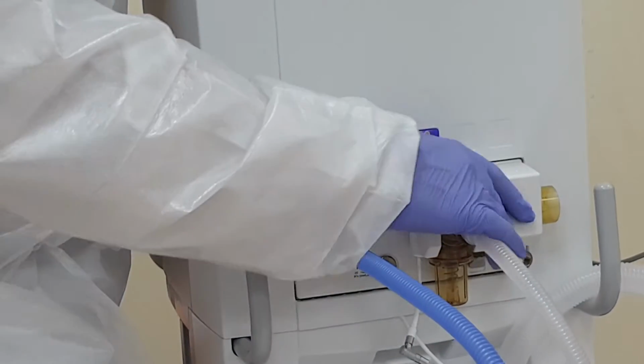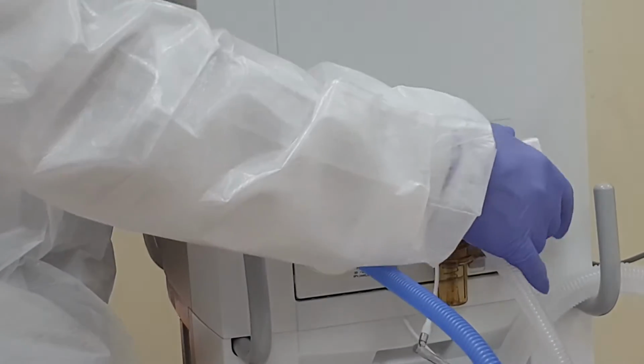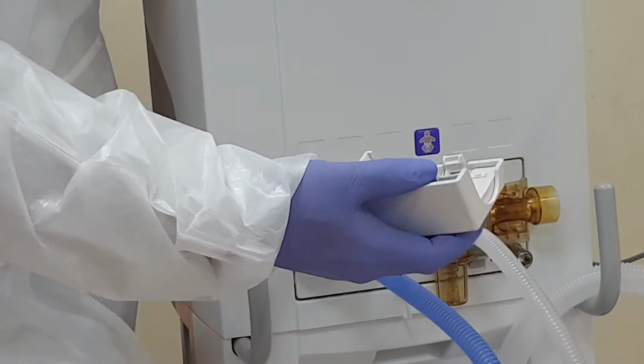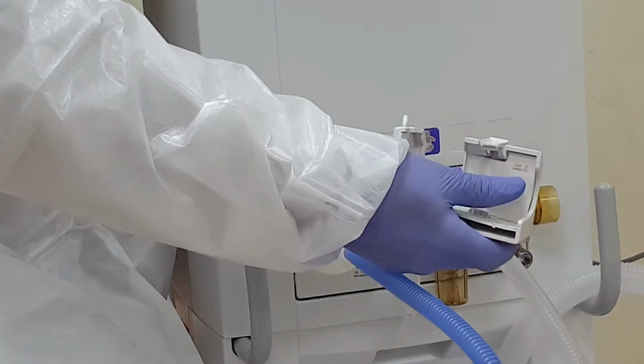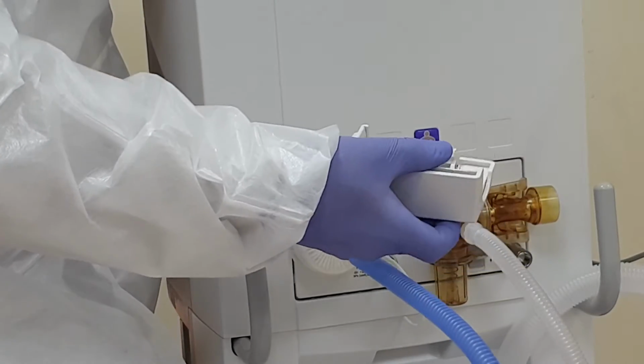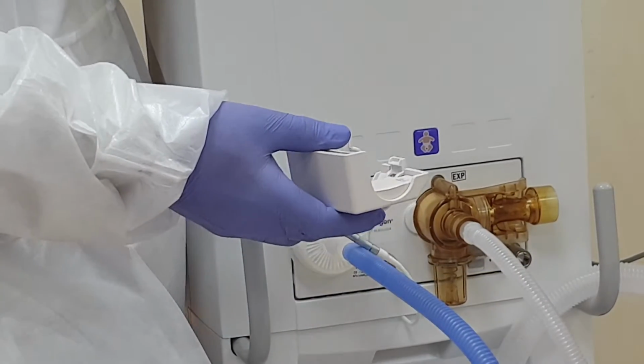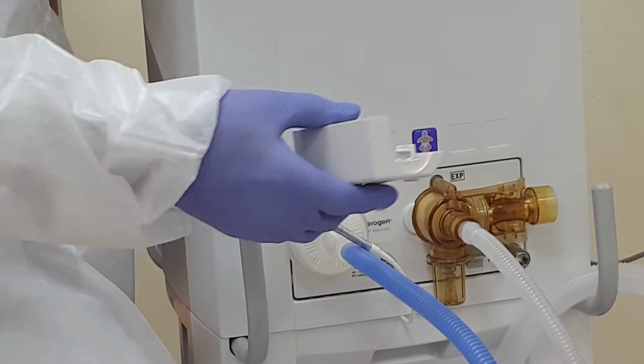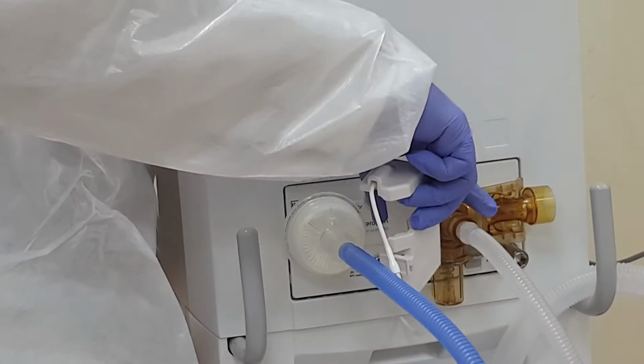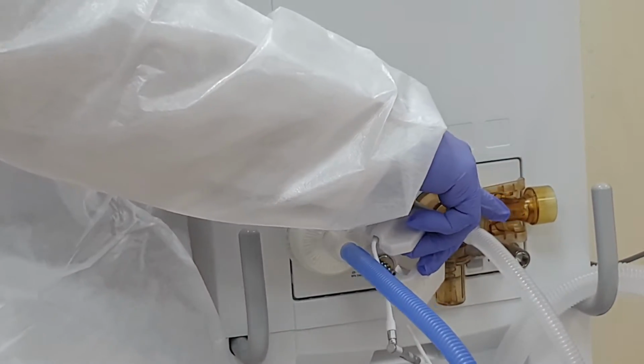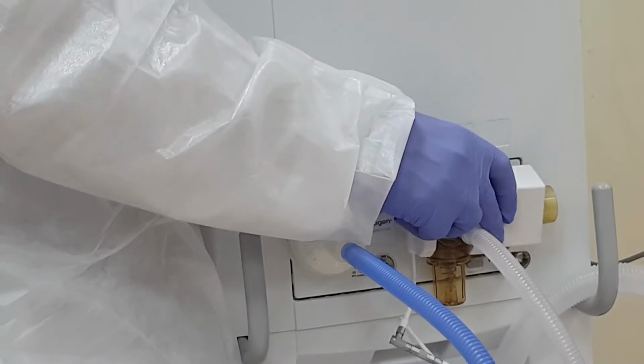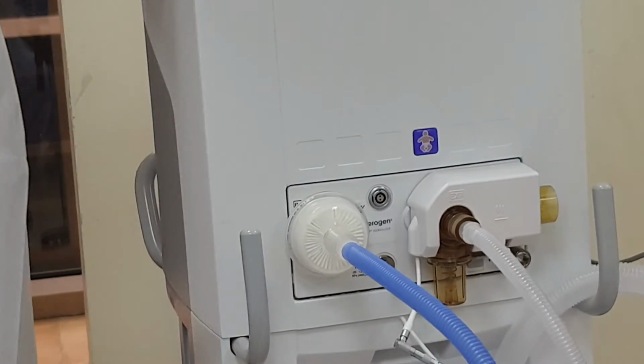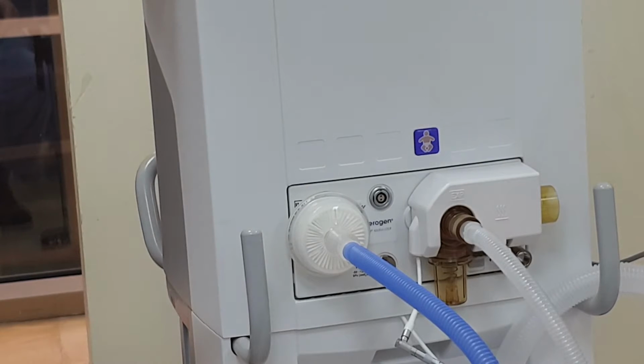Well, here we do have the expiratory port. Expiratory port has a cover. This cover, if you touch it, you'll feel some heat. Basically, what it does, it minimizes condensation that builds up in the flow sensor. So basically, it prolongs the life of the flow sensor because it doesn't get humid easily.